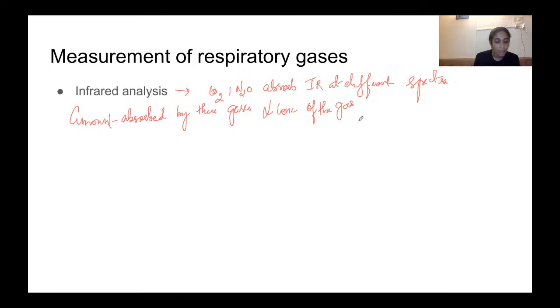Okay, so after the sensor detects the infrared energy, an electrical signal is produced, amplified, and the concentration is displayed. So the infrared analyzer selects the appropriate infrared wavelength using a filter to maximize the absorption of the selected gas at its peak wavelength. So the analyzer selects the infrared wavelength.